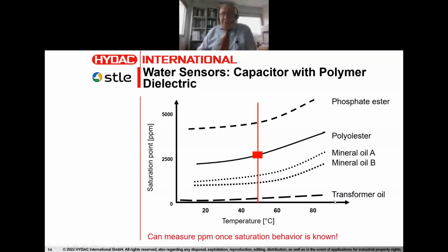It's also very interesting, because we can immediately also see the rather dramatic differences among all the various oil types. So transformer oil, being naphthenic based stock, is typically very, very low. It can tolerate water to a very, very low extent. So its saturation point is very, very low. So what we see here is, for example, even at very high temperatures, it will be saturated with very small water amounts, let's say 100 ppm or so. Typical mineral oils, depending on the base stock and depending on the additive package, this saturation level is going to go up. For typical mineral hydraulic oils, this may be somewhere in the neighborhood of 200 to 300 ppm range. Polyolesters are already much more polar, so they will go up even higher. And phosphate esters, which are even more polar, will go even higher.